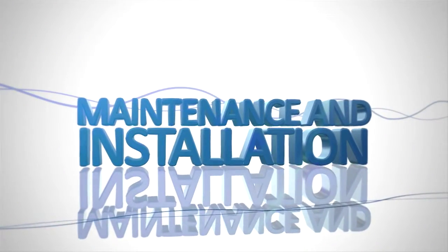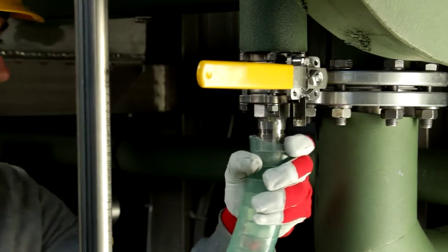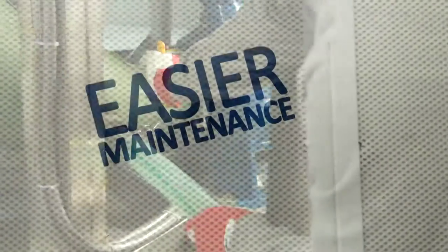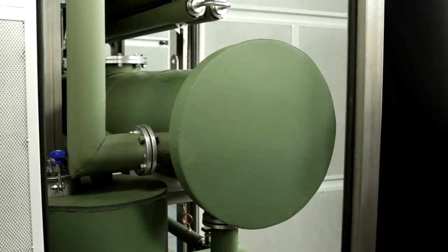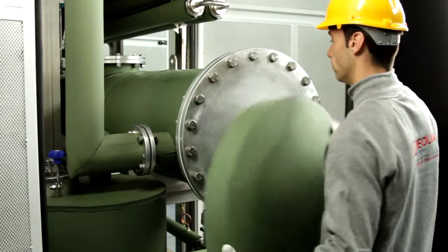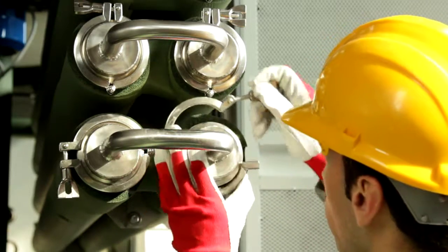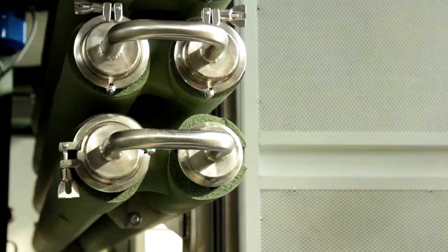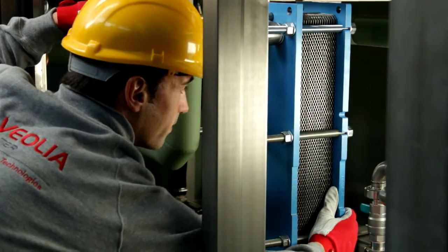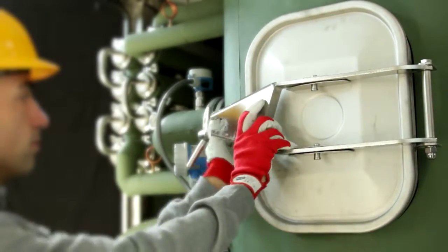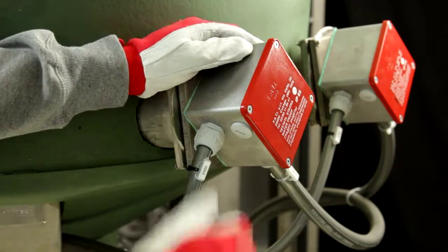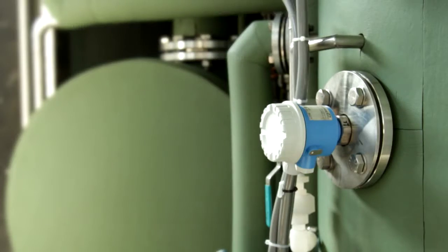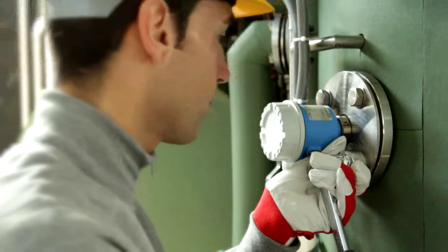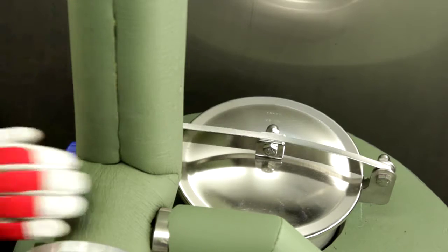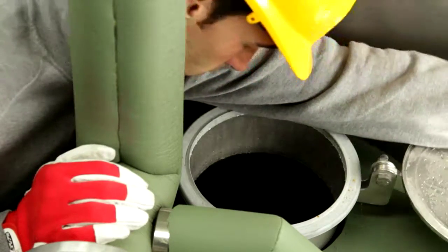Special care has been given to all aspects of maintenance and installation. Access to all components is now easier, and maintenance and assembly have been simplified. Condenser positioned at eye level. Easy disassembly of the thermal recovery unit. Plate heat exchanger at eye level and easy to disassemble. Boiler opening manhole. Its resistors allow a quicker startup. Floating level, easily extractable for cleaning with no contact with the wiring system. Distillate tank, separated from the heat exchanger, top access through the manhole.